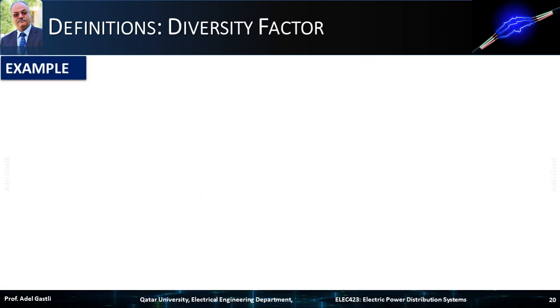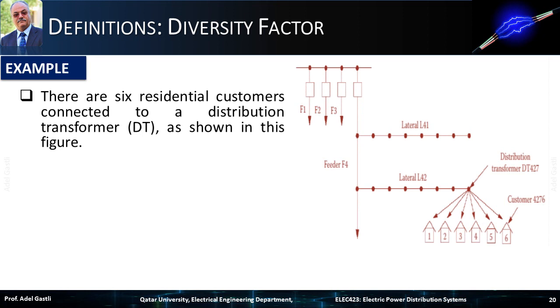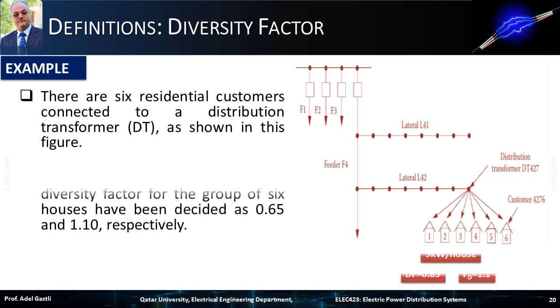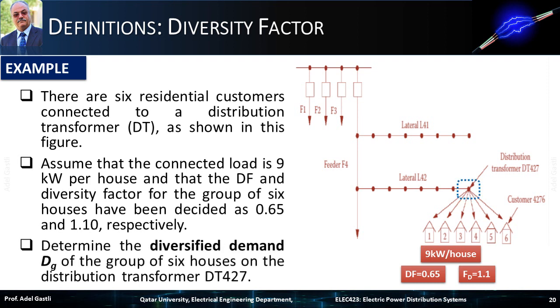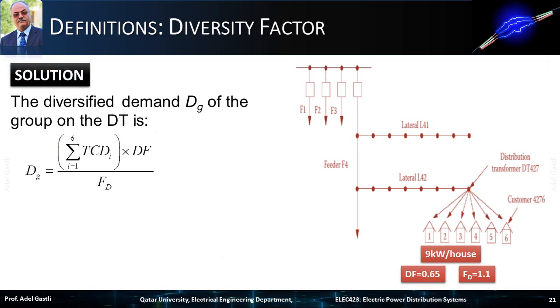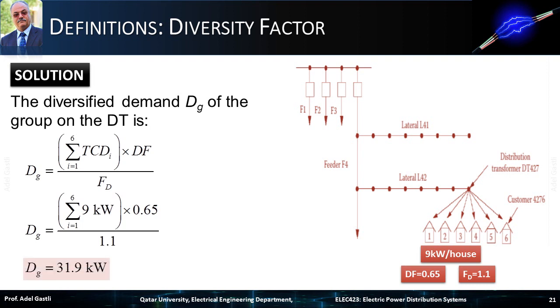Let's consider a second example. There are 6 residential customers connected to a distribution transformer. Assume the connected load is 9 kW per house, and that the demand factor and diversity factor for the group of 6 houses have been decided as 0.65 and 1.1, respectively. We want to determine the diversified demand of the group of 6 houses on the distribution transformer DT427. Using the diversified demand equation — summing the 6 houses' total connected loads, multiplying by the demand factor, and dividing by the diversity factor — yields a diversified demand DG of 31.9 kW.